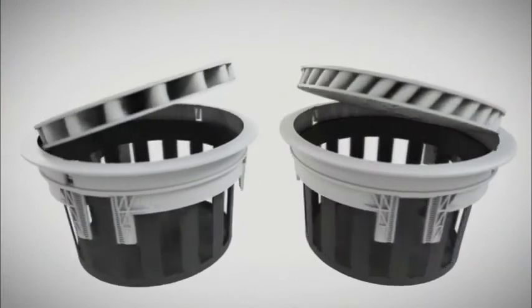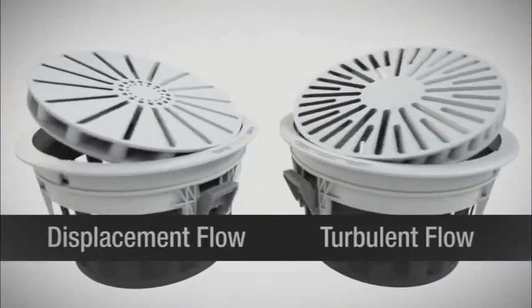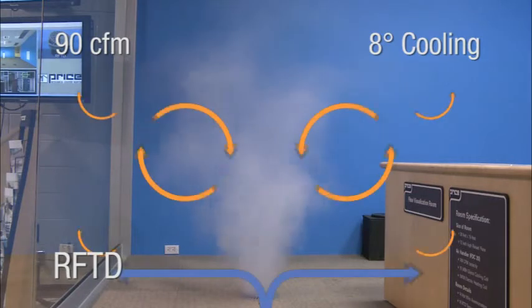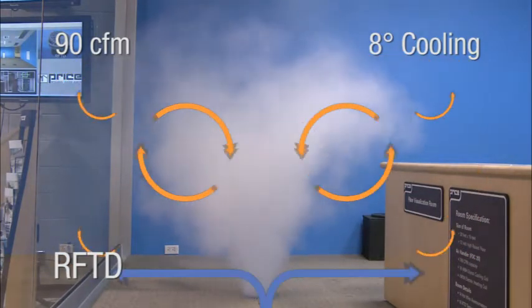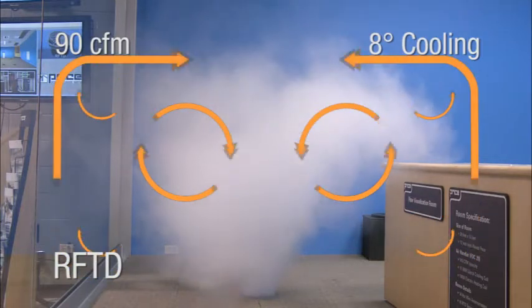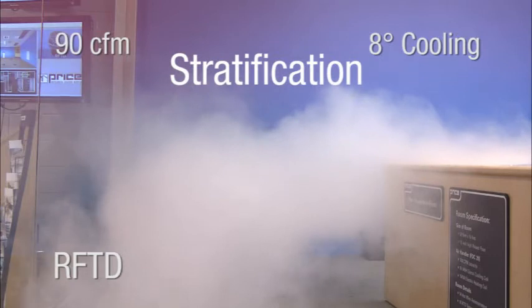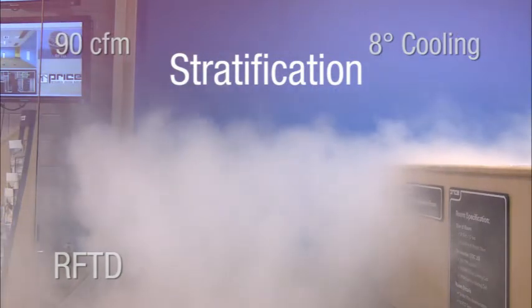Price offers two kinds of UFAD diffusers: turbulent flow and displacement flow. Turbulent flow diffusers discharge room air at around 400 to 800 feet per minute in a swirling air pattern that rapidly induces room air. This leads to room air that is mixed in the occupied zone — the first 6 feet from the floor. A stratification layer is formed at this point, leading heat and pollutants to collect at high levels above the occupied zone.